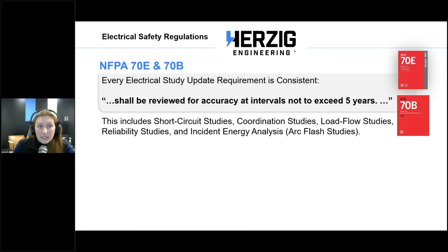Well, technically, it shall be reviewed for accuracy at intervals not to exceed 5 years. For all the studies and the diagram requirements, it is very clear. Intervals not to exceed 5 years, you quote unquote review it for accuracy.